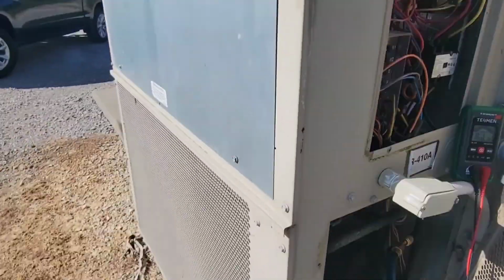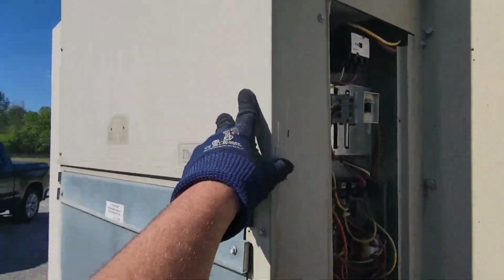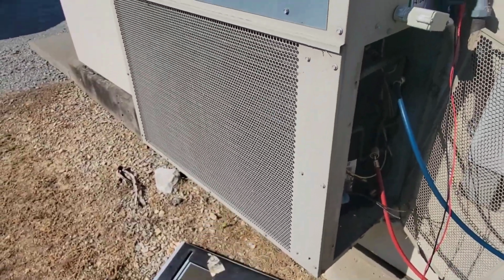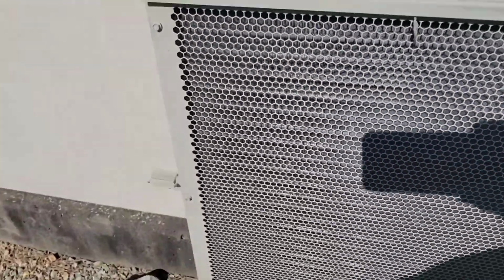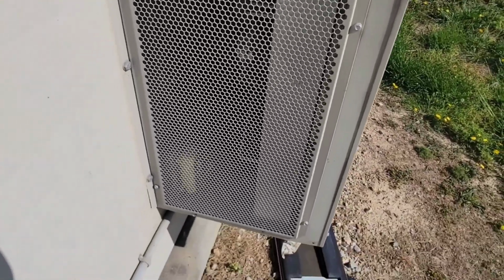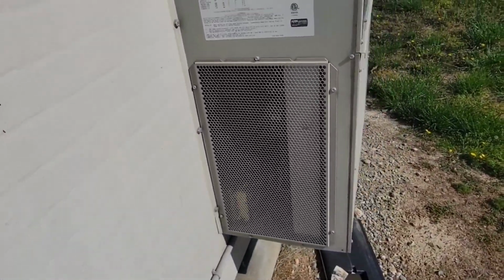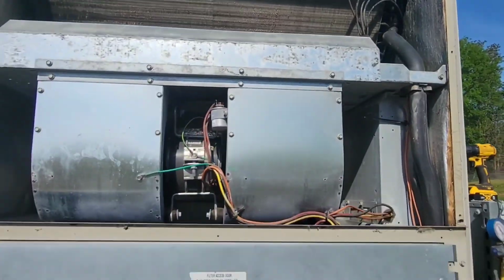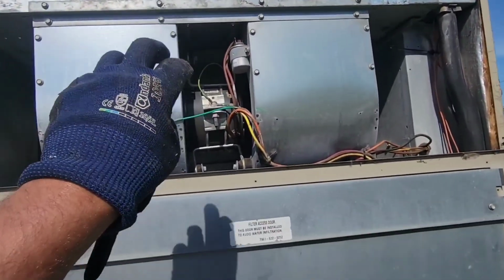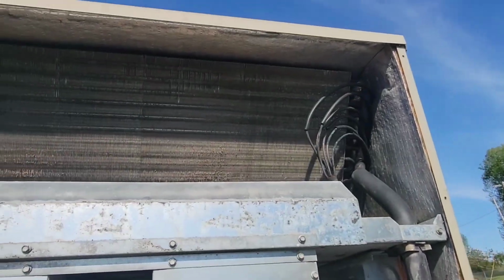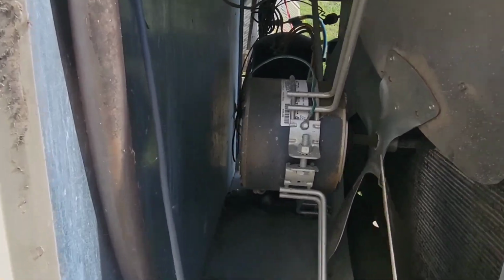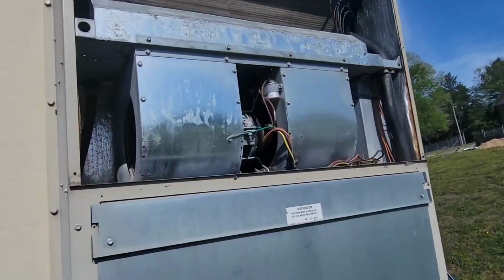Disconnect off. I'm going to open this up so I can get to the indoor coil. Go ahead and start with my leak detector and then visually look and see if I can find any sign of any oil. Got the panels off. You can see the indoor motor. You can see the indoor coil up here. And I got this panel off too. So you can see the condenser fan. You can see the coil. See how dirty it is.